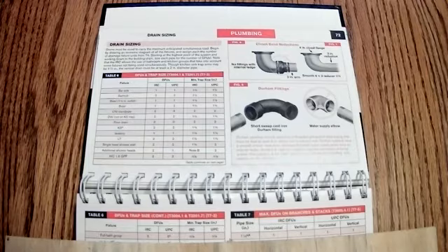Now, again, mainly they're talking about trap sizes here. They're not talking about drain sizes. Drain size is going to be a little bit different. Okay, so here again, we've got the lavatory, which is 1 fixture unit each, and they're talking about 1.25 inch drains. Now, again, I think that they should be 1.5 inch traps, really. They tend to plug with hair a little bit more, but 1.25 inch is all they're requiring. Single head shower stall, basically 2 fixture units.